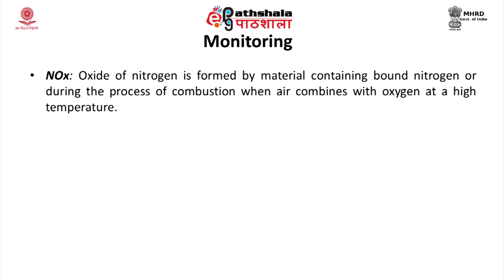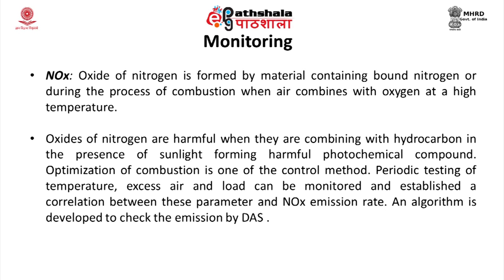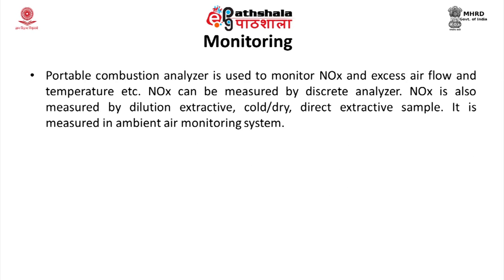Oxides of nitrogen are formed by material containing bound nitrogen or during the combustion process when air combines with oxygen at very high temperature. Oxides of nitrogen are very harmful when they combine with hydrocarbons in the presence of sunlight, forming harmful photochemical compounds. Optimization of combustion is one control method; periodic testing of temperature, excess air, and load can be monitored to establish a correlation between these parameters and the NOx emission rate. NOx can be measured by discrete analyzers, and also by dilution extractive, cold dry, and direct extractive sampling. It is measured in ambient air monitoring systems.